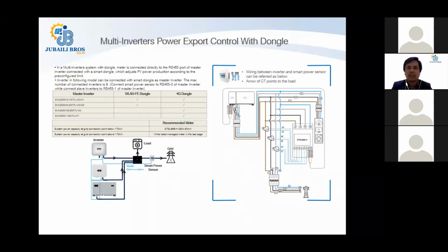So in such scenarios, you will connect the smart power sensor directly to our inverter and do the configuration for the zero export control. Again, in this scenario, the limitation applies that our Huawei power sensor can be used up to a 170 kilowatt PV system. And above this size of a PV system, you should look into one of the power meters that are recommended by Huawei from a third party.